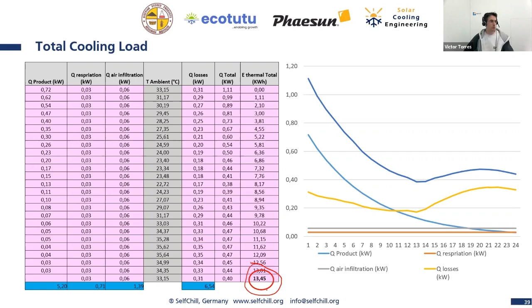Happily for us, because we are using vapor compression heat pumps, and they work with a coefficient of performance. This means they deliver more cooling energy than what they consume on electricity, if you remember from our last webinar. This is calculated or described with the coefficient of performance, COP. So the efficiency of refrigeration systems is measured by COP, which indicates a ratio between the extracted heat, or the cooling power, divided by the electrical power or the energy consumption.